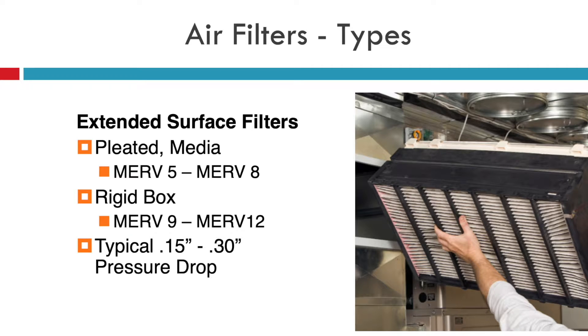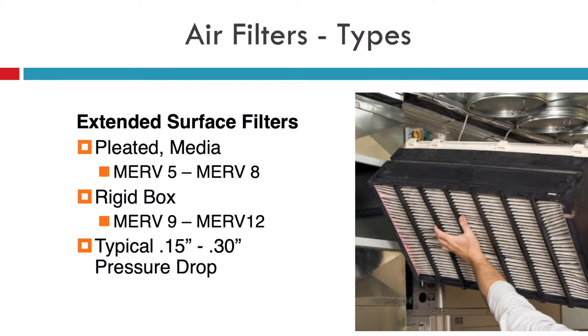The next option is what we call an extended surface filter — in the industry, a high efficiency or large pleated filter. It's usually made up of media and ranges in the MERV 5 to 8 range typically. The more pleats and the thicker the filter, the longer that filter can last in the system and the more it can hold. There are also, under extended surface filters, things called rigid box filters. Those are made typically by OEM manufacturers and might have a slightly higher efficiency value, typically MERV 9 to 12, and tend to have a higher pressure drop.